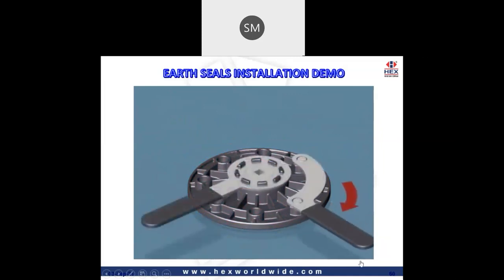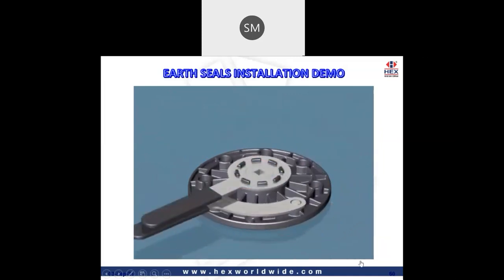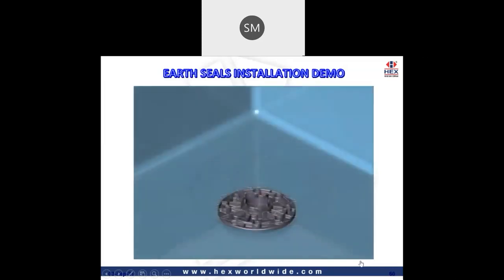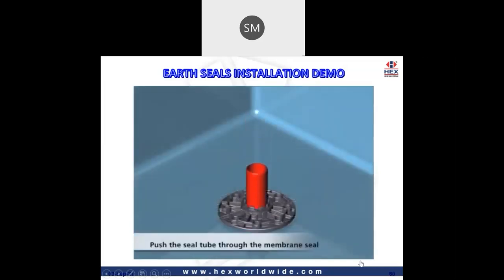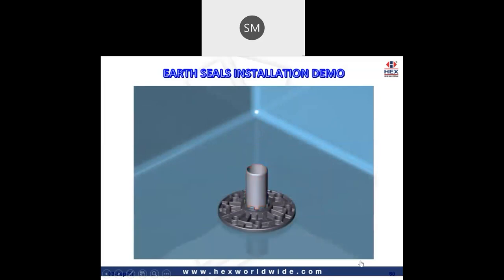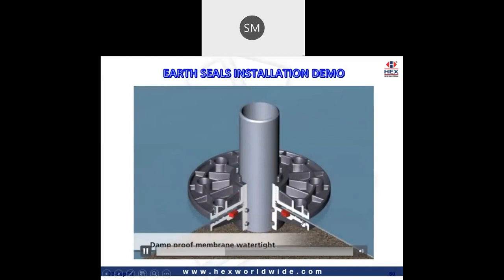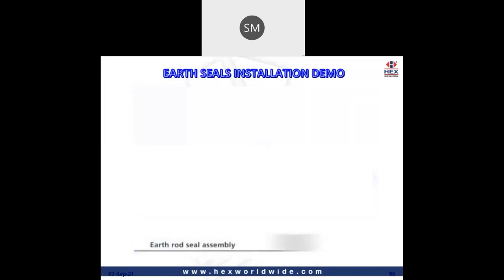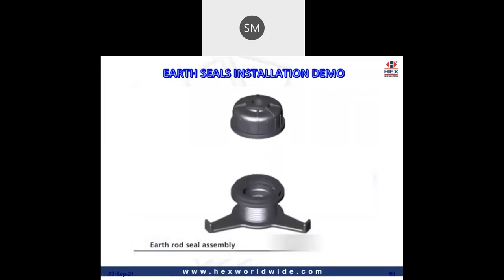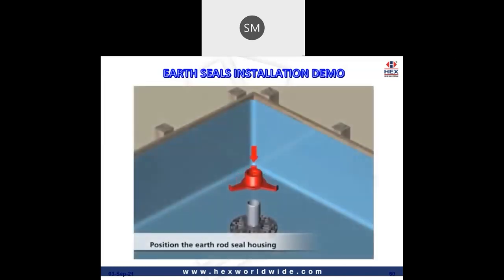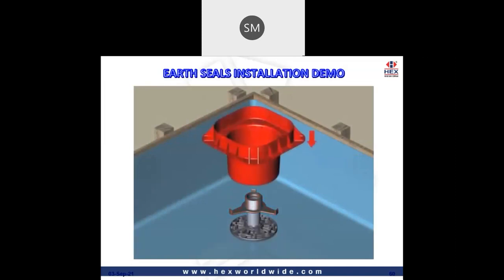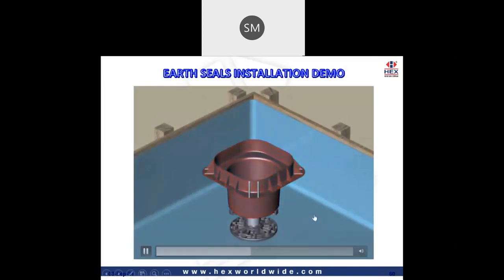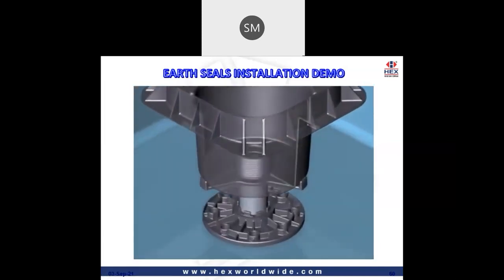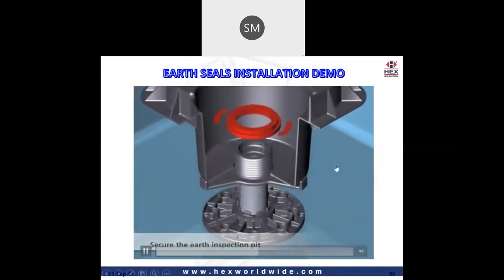Now after it is tightened to the required tightness, the seal tube is then inserted into the membrane seal. If you see the cross section that will be coming up, you can see that it is sealed watertight. You have seals here, here, and here at three locations, so the water cannot enter. Then we move on to the top part of the seal assembly. The top flange is opened up and it is placed on top of the seal pipe. The earth pit chamber is then placed on the top of the top flange, and it is locked into place using a nut.